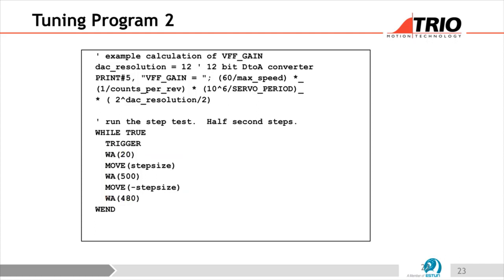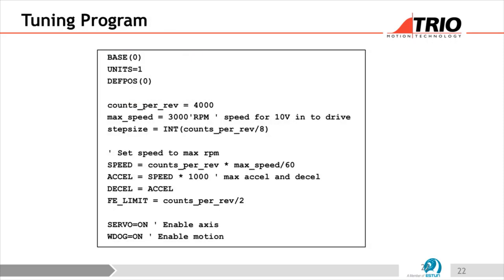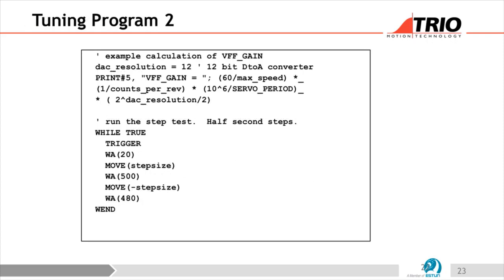The code above the motion loop is not used in the program itself — it's just an example of how to calculate VFF gain. It prints to terminal channel 5 what the VFF gain would be given the values of 4,000 counts per turn and 3,000 RPM used in the calculation.